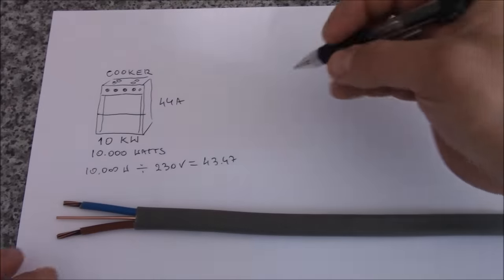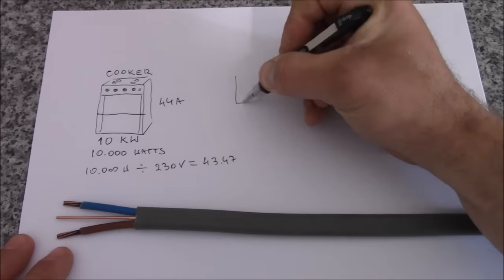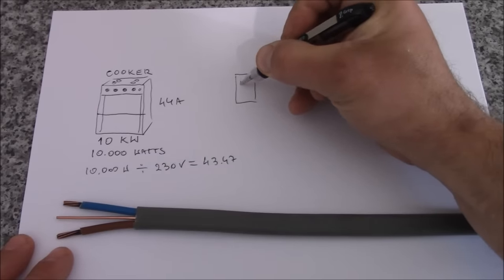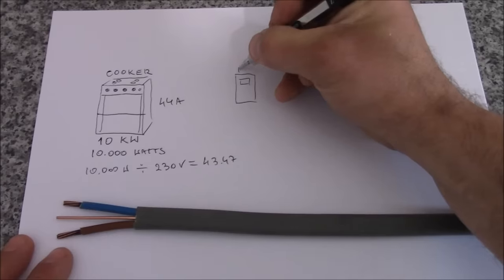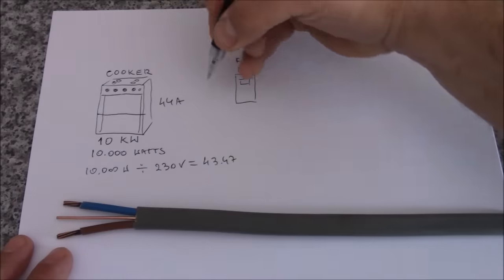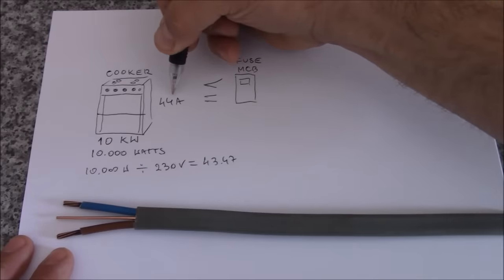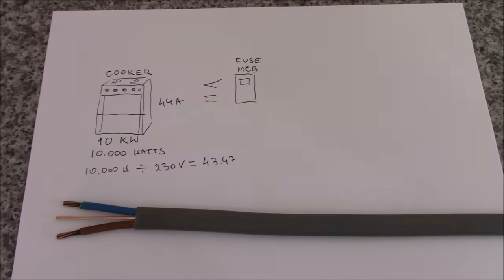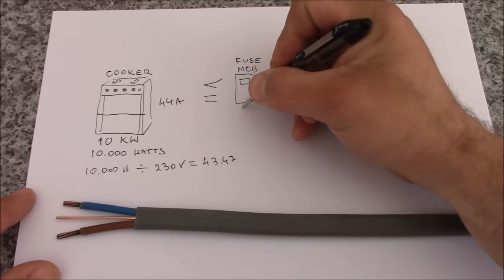So now we need to choose the circuit breaker or fuse. I'll draw it like this. So let's say this is the circuit breaker. And this has to be at least equal or bigger than the cooker. So we can install 45 amp fuse or MCB.